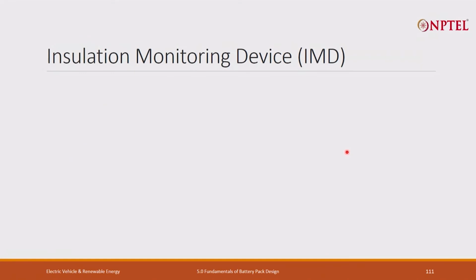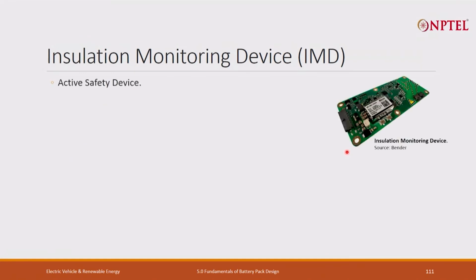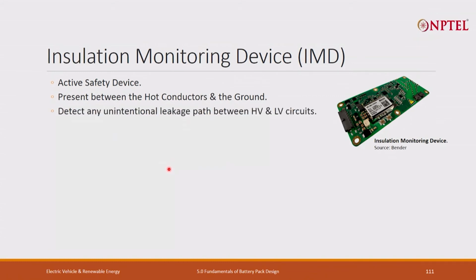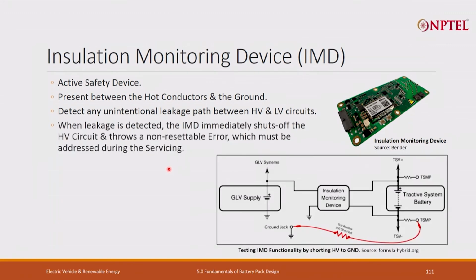Then next comes the insulation monitoring device. It's an active safety device. It's present between the hot conductor and the ground. What it does is it detects any unintentional leakage that happens between the hot conductor and the ground. When leakage is detected, the IMD immediately shuts off the HV circuits, and generally throws a non-resettable error which you cannot reset, because now the problem is there.